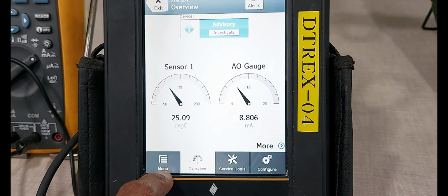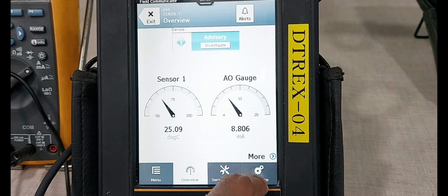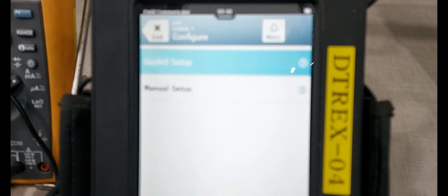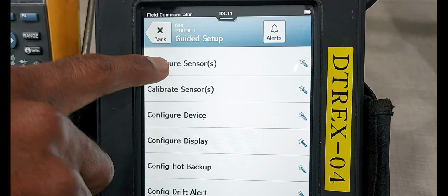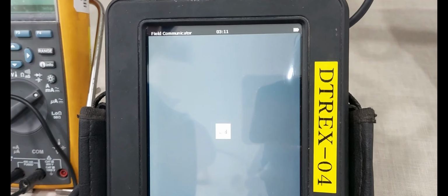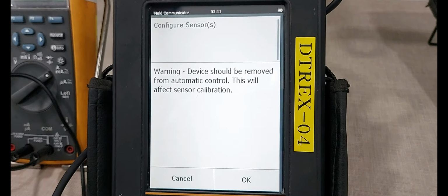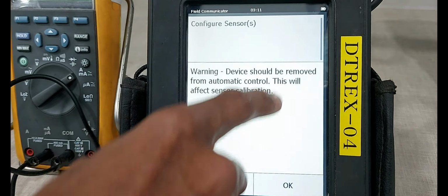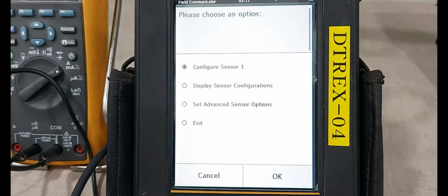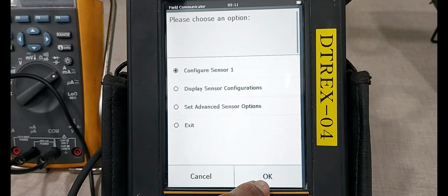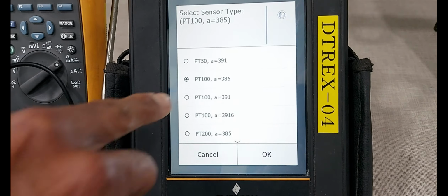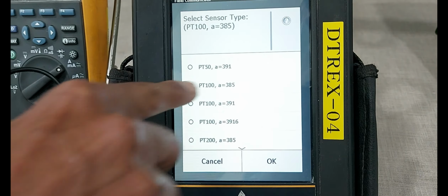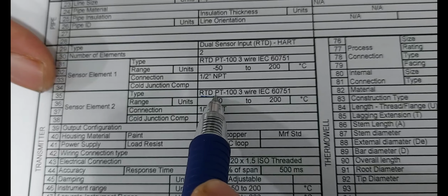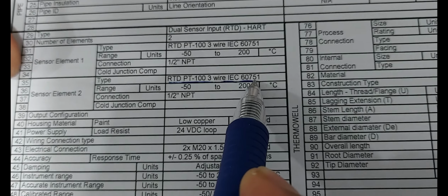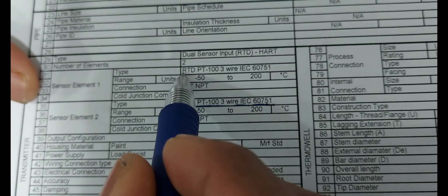Next we are doing the configuration of the temperature sensor. Select the configuration menu. First select guided setup and configuration of sensor. Okay, we are moving from automatic control to manual mode. Configuration of sensor 1, select it. PT100 385, alpha value 385. RTD PT100 3 wire, IEC standard 60751. Both are the same.